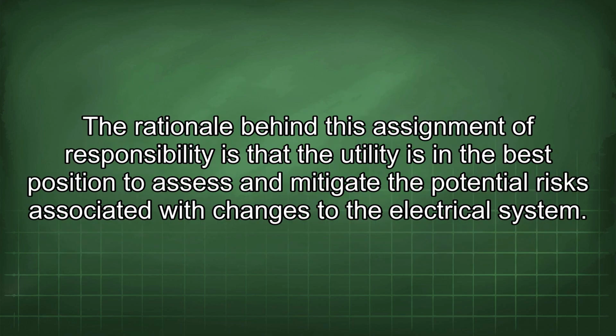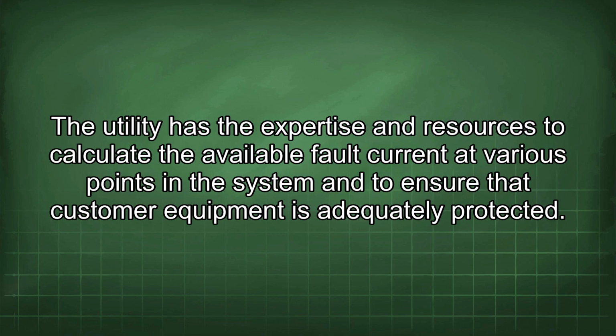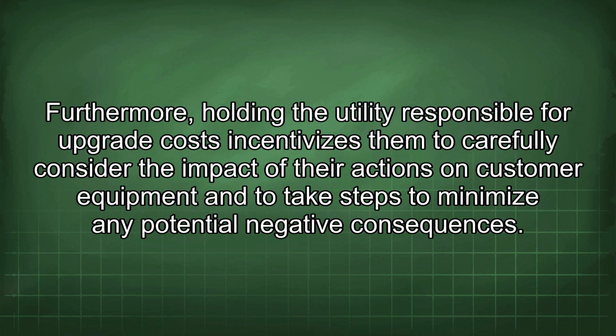The rationale behind this assignment of responsibility is that the utility is in the best position to assess and mitigate the potential risks associated with changes to the electrical system. The utility has the expertise and resources to calculate the available fault current at various points in the system and to ensure that customer equipment is adequately protected. Furthermore, holding the utility responsible for upgrade costs incentivizes them to carefully consider the impact of their actions on customer equipment and to take steps to minimize any potential negative consequences.